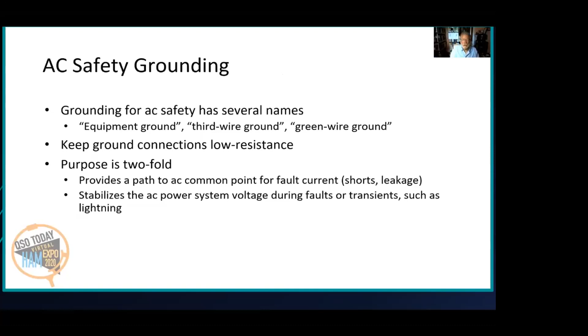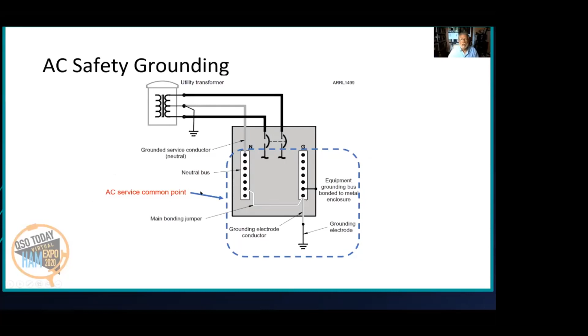If you open it up and look at it, you'll see two big buses. One is for the neutral. This is all the white wires. This is where all the green and the bare wires go. These are usually connected together at your service panel. That's connected to the metal of the enclosure, and that's connected to the outside grounding electrode, which is probably a ground rod or two. Everything inside this blue outline is your AC service common point. That's where your AC service safety grounding goes.